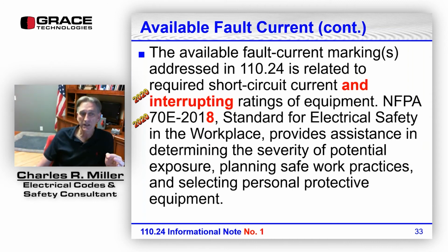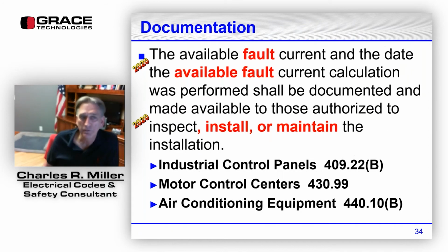It says this standard for electrical safety in the workplace provides assistance in determining the severity of potential exposure, planning safe work practices, and selecting personal protective equipment. The available fault current, it used to say available short circuit current, was changed to available fault current, and the date the available fault current calculation was performed has to be documented and made available to those authorized to inspect, install, or maintain the installation.